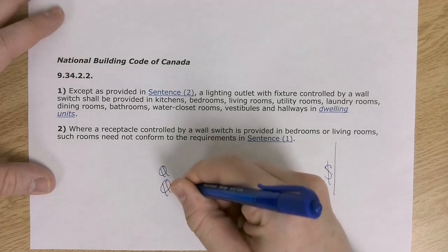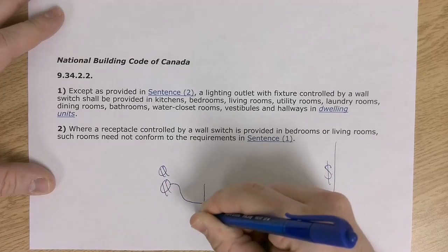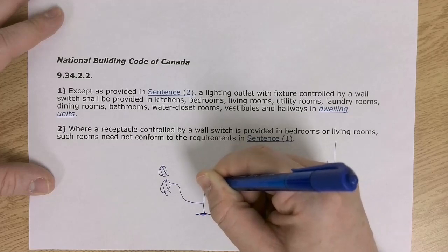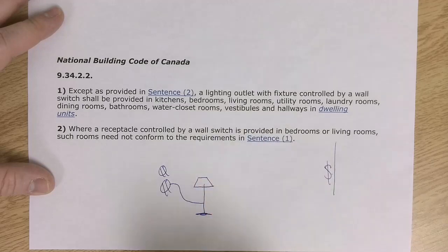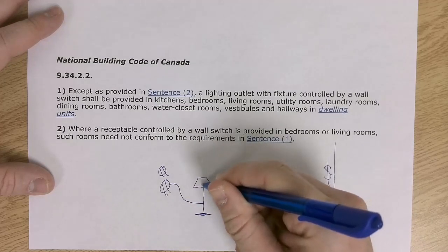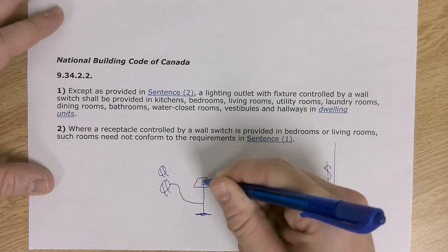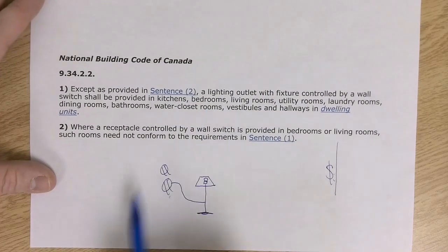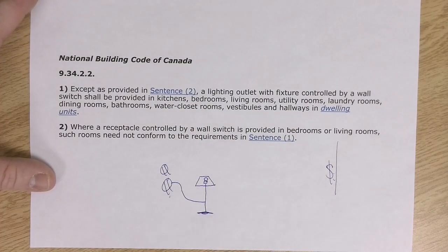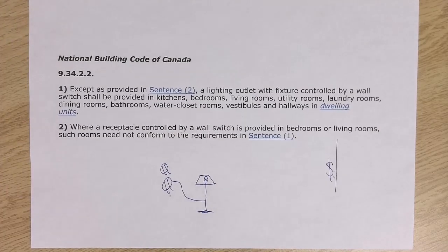When you plug a lamp in, which may be confusing because we're in the lighting section, when you plug in one of these standalone lamps, which is actually a luminaire, as we know now, and you got your bulb in there, and this switch turns on this half of the receptacle, the building code is saying, yeah, that counts as an outlet for lighting. So I just wanted to sort of explain where we find out how to put lights in to code, and it's not in the electrical code, it's in the building code.